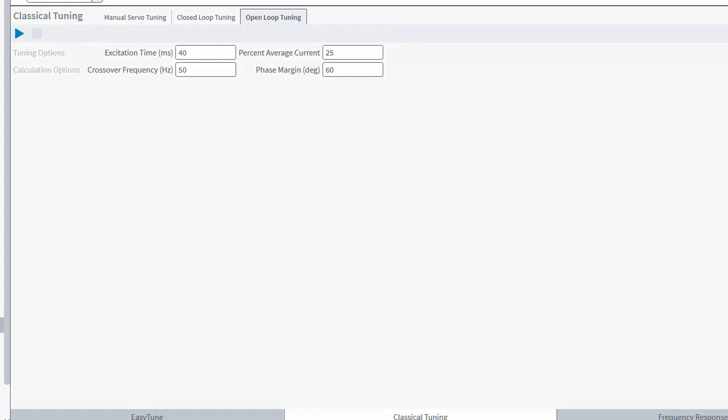Let's start with the open-loop tuning. This will input an open-loop current into the system. This is typically used when you have no starting gains to use and you just need some sort of starting tuning values to get you started. To do this, select an excitation time as well as an amount of current that's represented as a percent of the drive's peak current potential.